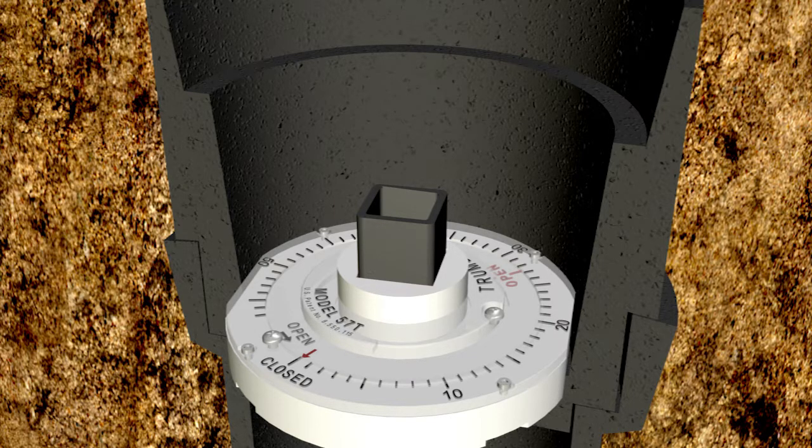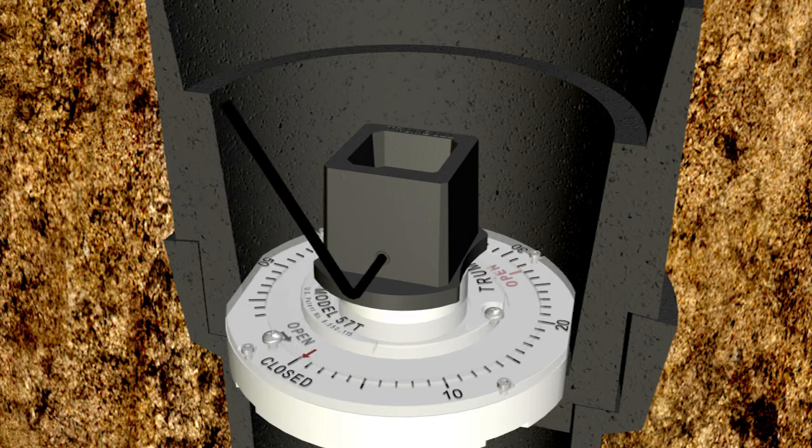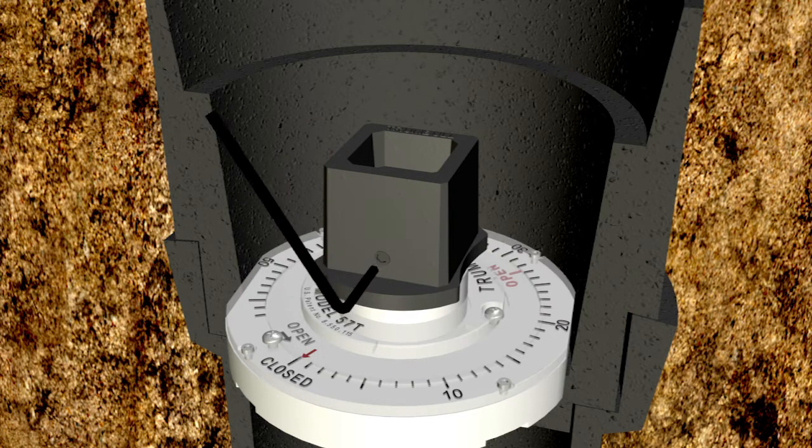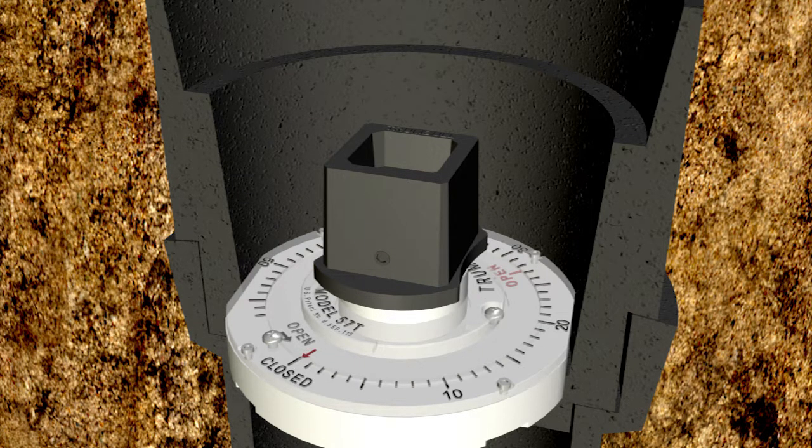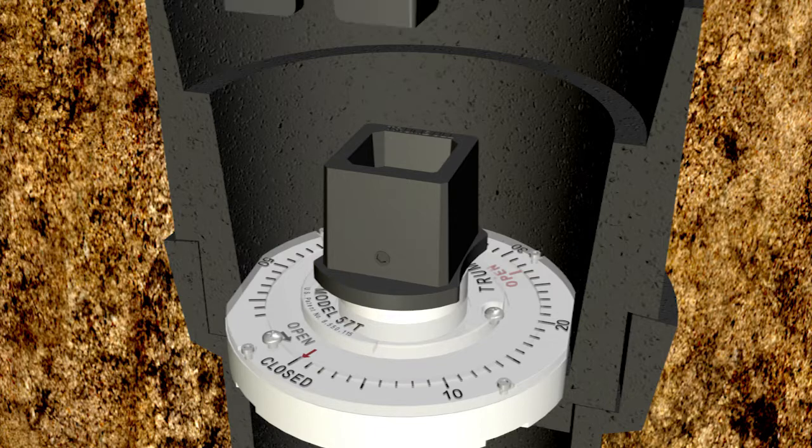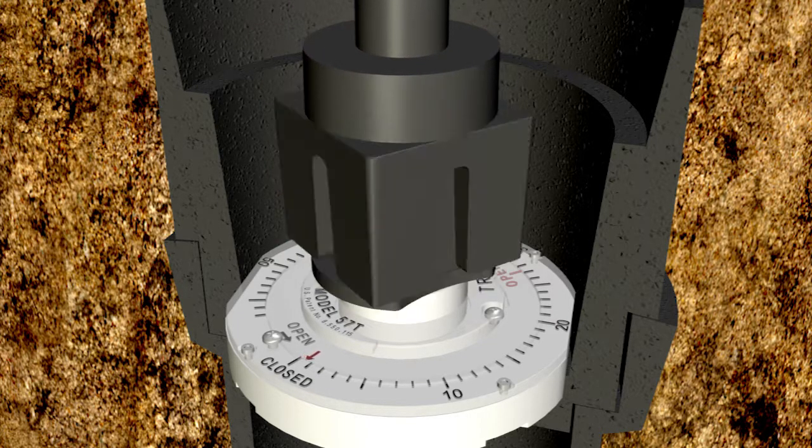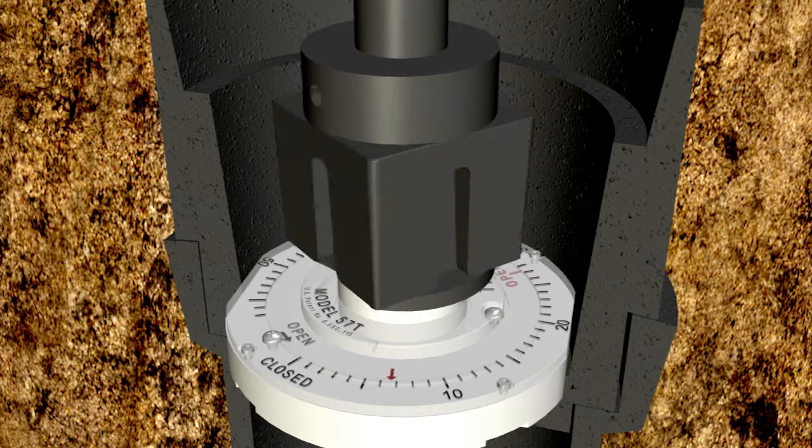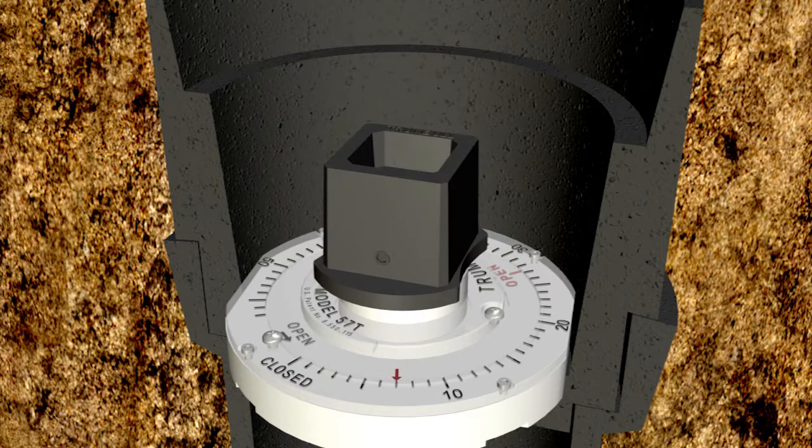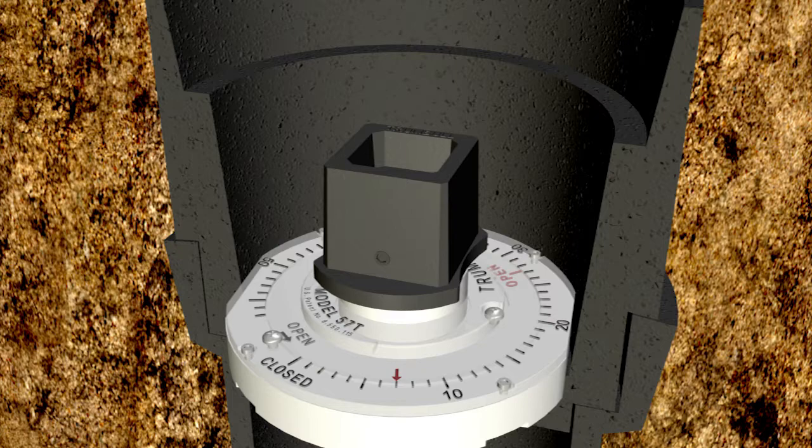Place the two inch operating nut onto the extension stem and tighten the set screw. To calibrate the position indicator, first fully open the valve. Note the red indicator arrow now points to the number of turns required to open this valve.